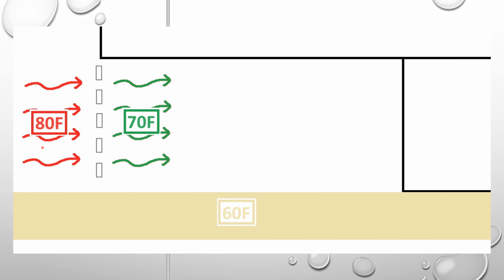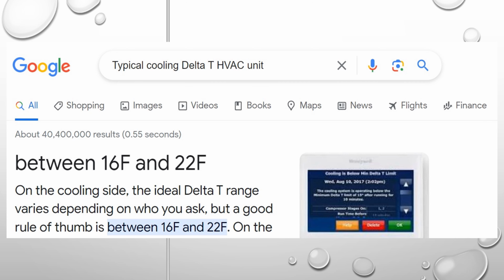All right, so now I got two factors in here on what's happening in this crawl space and my surrounding area. So the next factor I have to find out is, what's the temperature of my air? What is the temperature of my supply duct? Even though I already knew the answer to this question, I Googled it anyway. So I typed in typical cooling delta T of an HVAC unit. What that really means is the difference between the return and the supply. So typically you find 16 to 22 degrees Fahrenheit. A lot of our systems that we put in, typically we end up around 20 degrees Fahrenheit. So in easier terms, if you set your thermostat to 70 degrees Fahrenheit, more than likely your supply air is going to be 50 degrees Fahrenheit. So I used 50 degrees Fahrenheit as the temperature inside the ductwork.